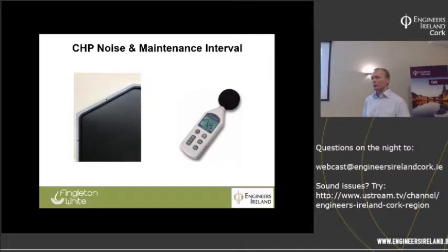So it's a big service interval, but the loading on the engine is not too high, and we operate at low RPM. There are two reasons to operate at low RPM. One is the noise issue, and the other is service interval, to lightly load the engine. Another thing is an extended oil sump, so you have a large capacity in your oil sump. That's really for the maintenance interval.